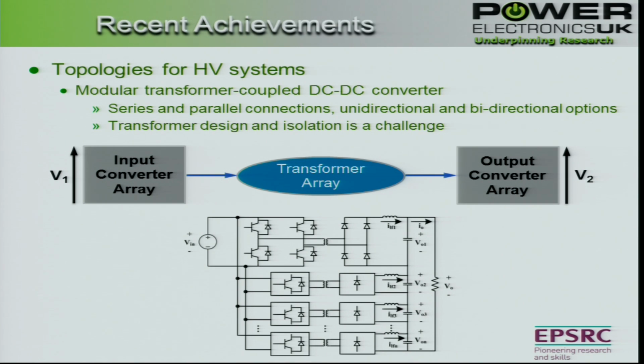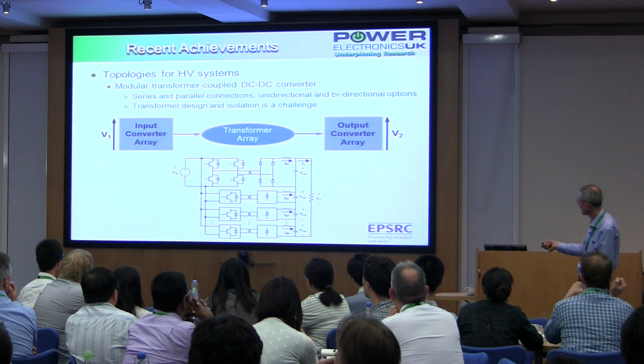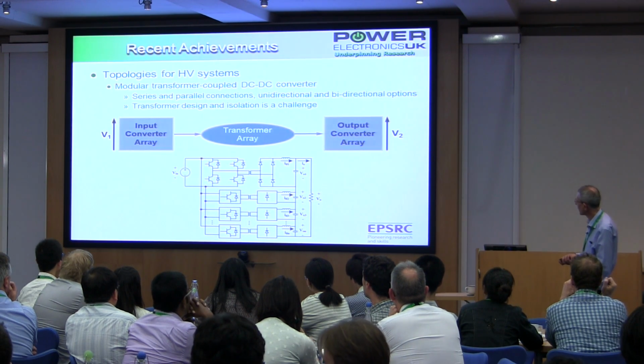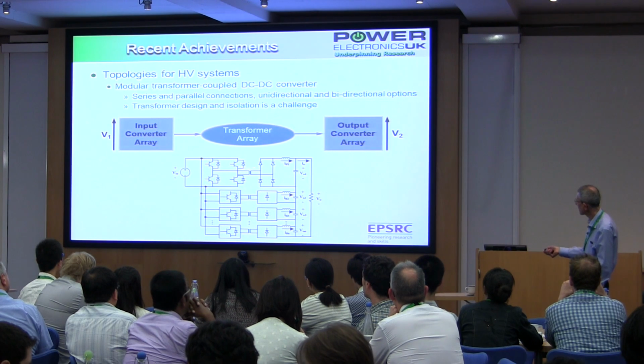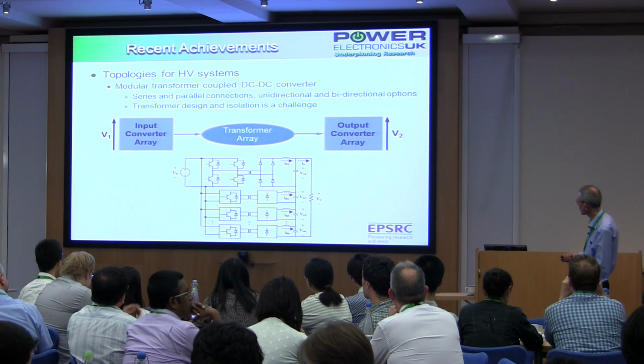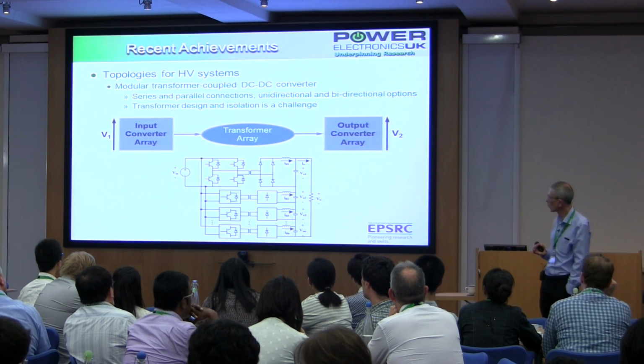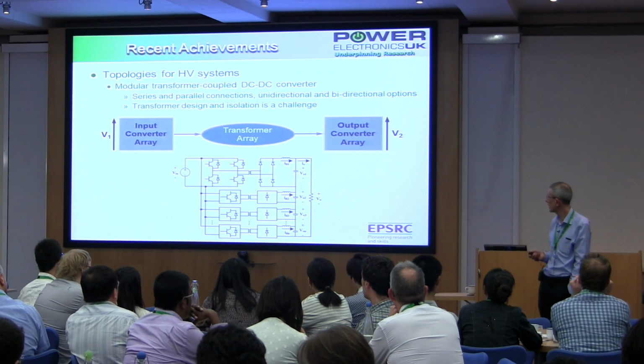We could have an active bridge on the right-hand side to produce bidirectional power flow. The challenge with these systems is that the individual transformers have to cope with the total voltage on the DC side because of the way it's organized. So this one, at the top of the string on the right-hand side, is still paralleled at ground on the other side, so it sees the full voltage of the output. So the design of those transformers and achieving isolation is a key challenge.